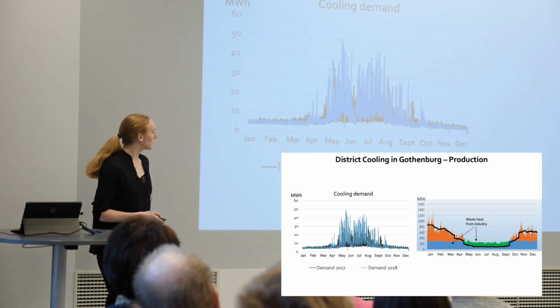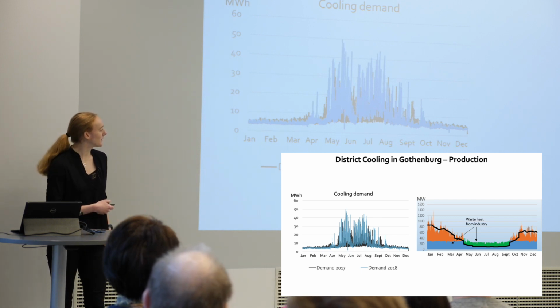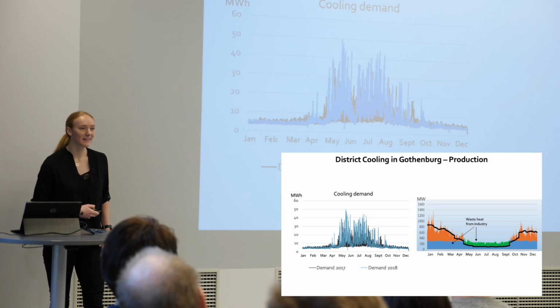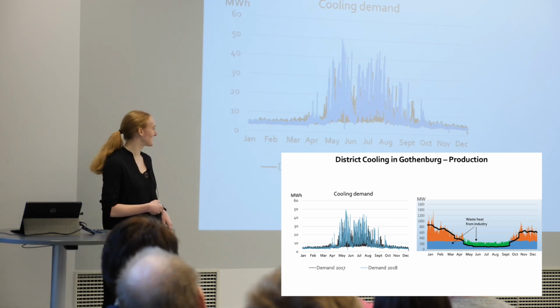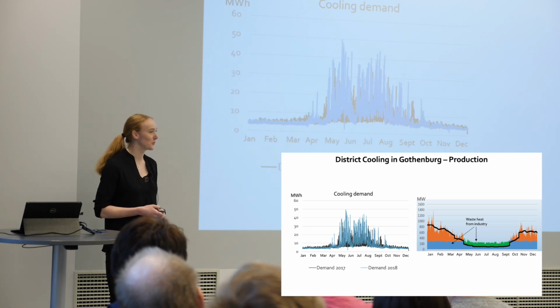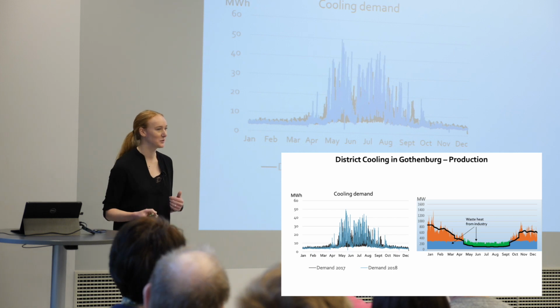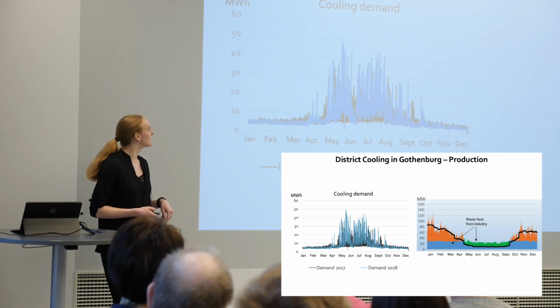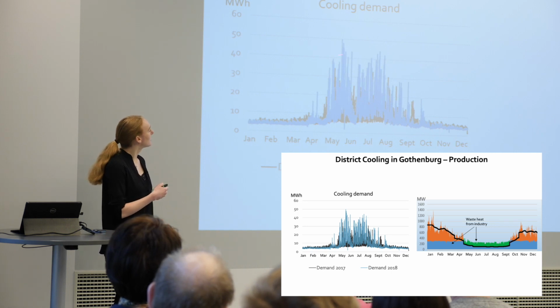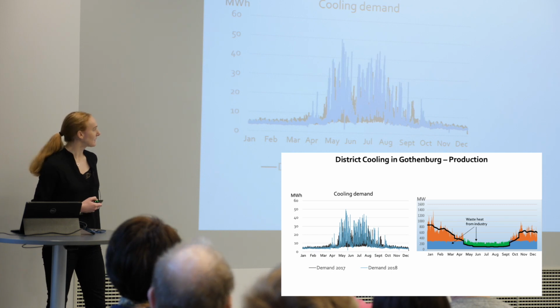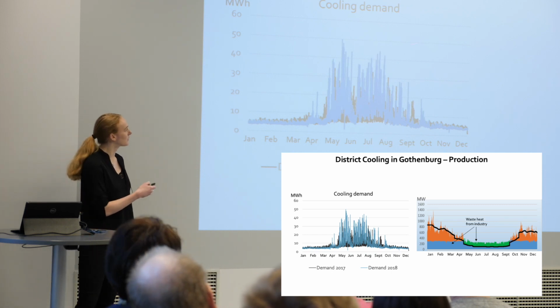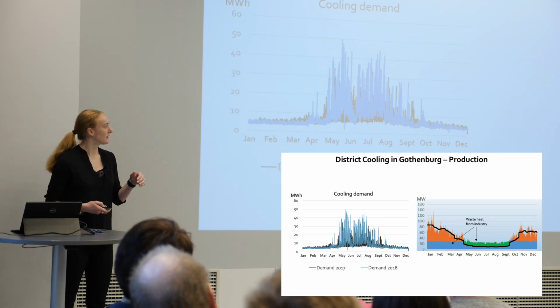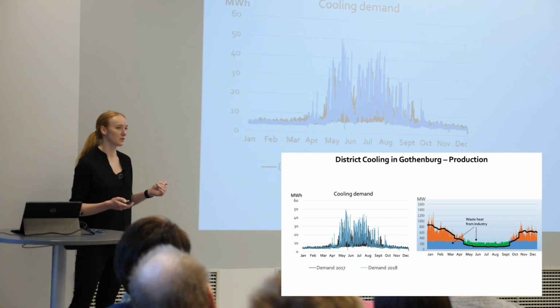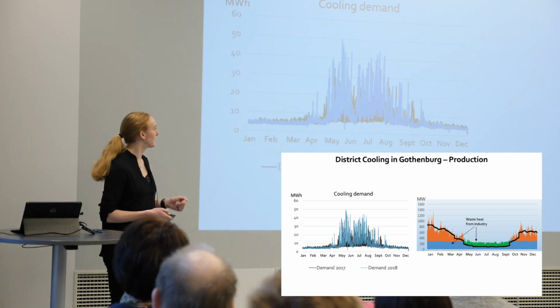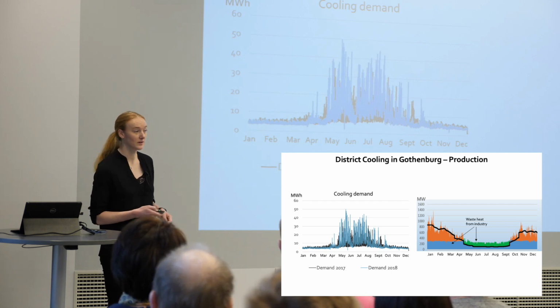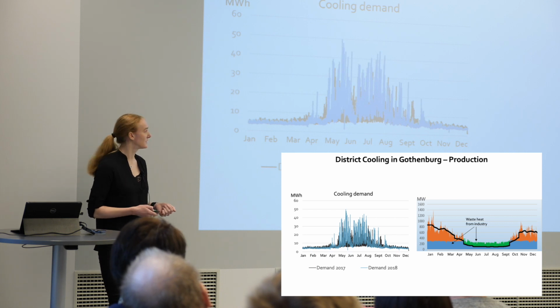This is the cooling demand of Gothenburg, and I wanted to show two different years, because these two years were very different in how nice the summer was. 2017 was a very cold summer, and 2018 was a really warm summer with heat records and an amount of hours with temperatures over 25 degrees that was far more than ever seen. So the cooling demand in 2018 was up to 50 megawatt hours at most. And these peaks were a lot higher than in 2017. So this shows that the outdoor temperature and the conditions during the summer very much decide what the cooling demand is going to be, and especially the peak hours in the summer, which is the tricky part for the production facility to meet.